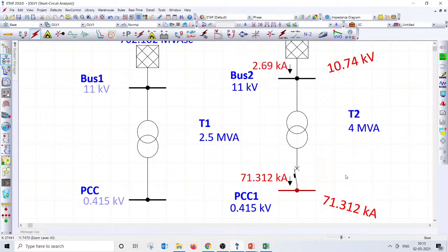So if you look at this 4 MVA transformer, the fault current is about 71.312 kiloamps. I have just gone with 4 MVA, and you can put up your impedance display here, right?